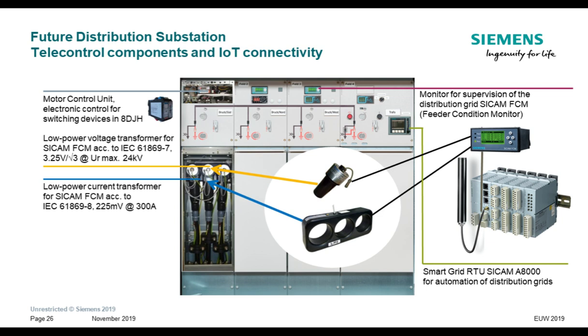The most important device for the supervision and monitoring of the sensors is the device on the right-hand side, this gray device, which is called feeder condition monitoring. We use this device for supervision of the different bays; it is connected hardwired to the sensors, and is able to measure precisely the current and the voltages, and can also indicate faults, overloads, earth faults, and directional earth faults. This feeder condition monitoring gives us quite a lot of insight into the medium voltage feeder itself. All these devices are later connected via protocol to the SICAM A8000, our RTU, our standard gateway to the future distribution substation.